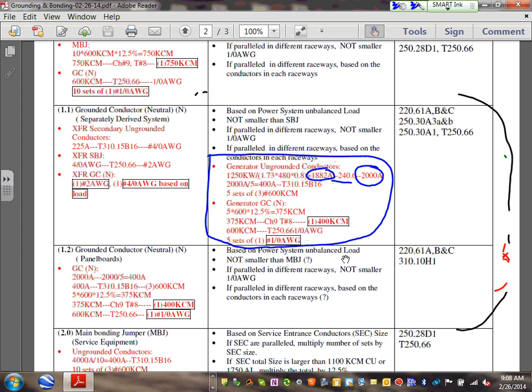If that was a baby generator, you know what you add here? You just multiply this one by 1.25, assuming it's continuous, if it was a smaller generator, say 50 kW. This is a big generator with big amps. These are power circuit breakers, electronic circuit breakers, so they will be 100% rated circuit breakers. So I have a 2000 amp overcurrent protection device. That's all I need to size my conductors.